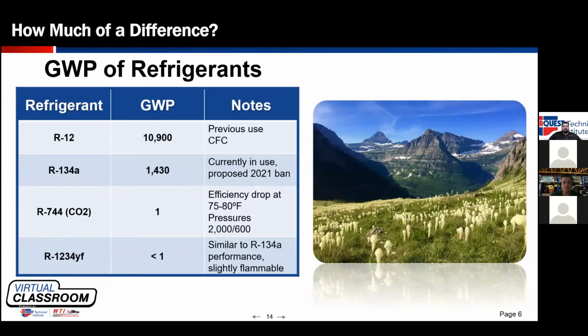What's considered a high global warming potential refrigerant is a refrigerant with a GWP over 150. So 134A was still 10 times too high. Refrigerants that came out as potential replacements were HFC 152A, CO2, and 1234YF. 152A, while it meets the GWP requirement with a GWP of 124, was ruled out because it is very highly flammable. 152A is commonly used as computer spray duster, and you can find videos on the internet of people basically lighting it on fire. It is flammable.